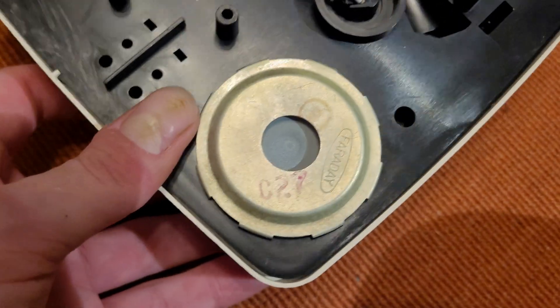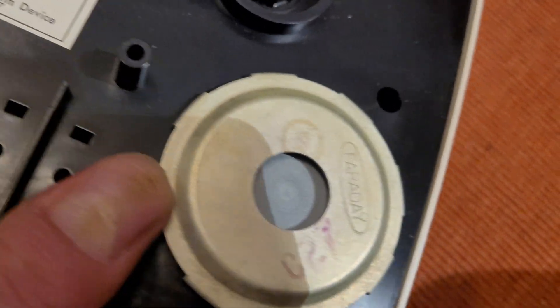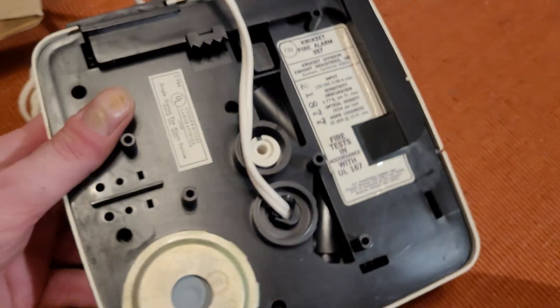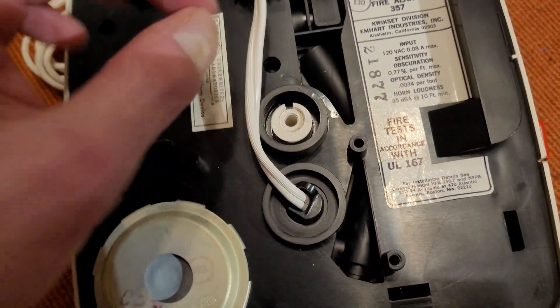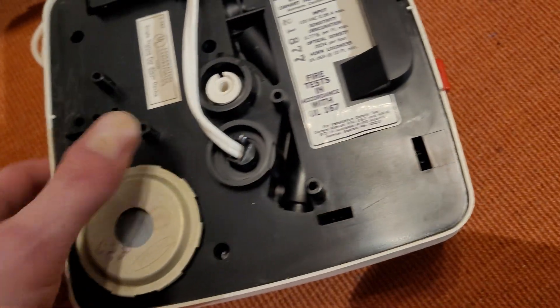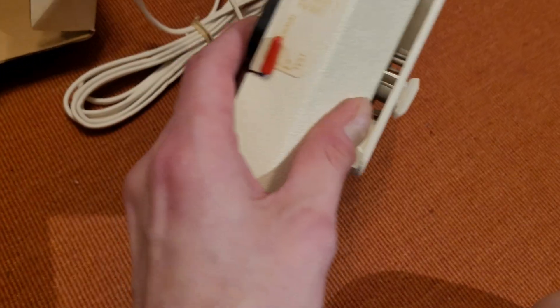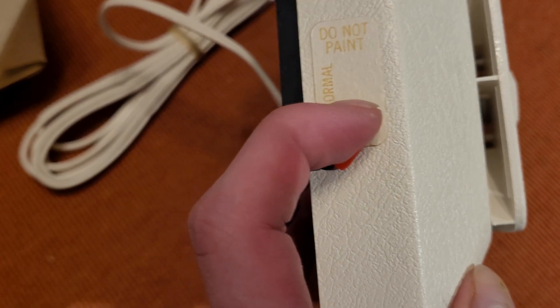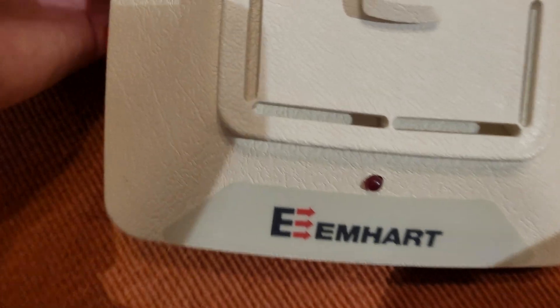The horn on these is facing out the back like this, and these normally have Faraday horns. Like this one, as you can see, has a Faraday horn. I know they often used other brands of horns — I think Delta Larm, possibly Edwards. You can also see on the back here some of the sensor workings. Here's the light tubes — one of them is for the LED that outputs the sensor beam, and one of them is for the photoelectric sensor itself. And then on this side here there is a test button — actually a little test lever on the side here, just like the ESLs and Newtones. And on top you have a smoke inlet to the sensor itself, with another inlet through the top vents. And then the LED indicator is right there.